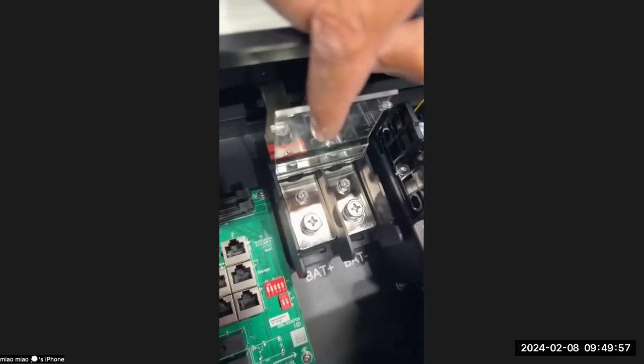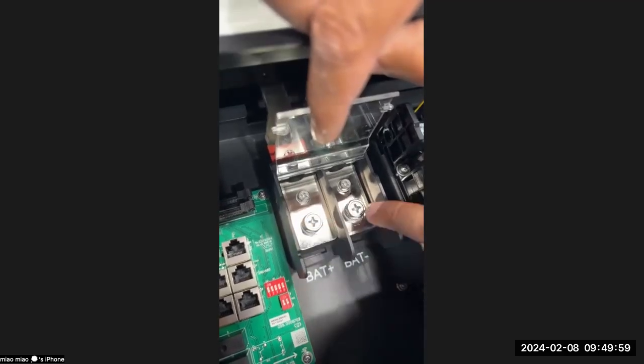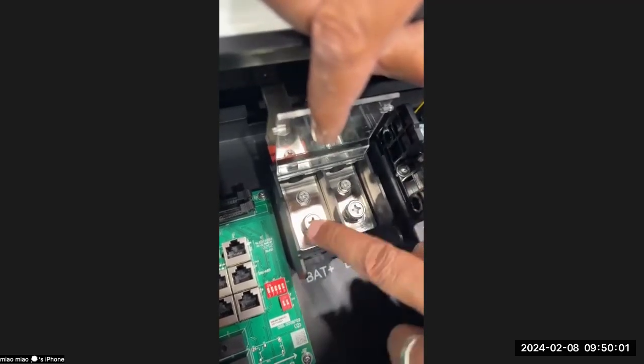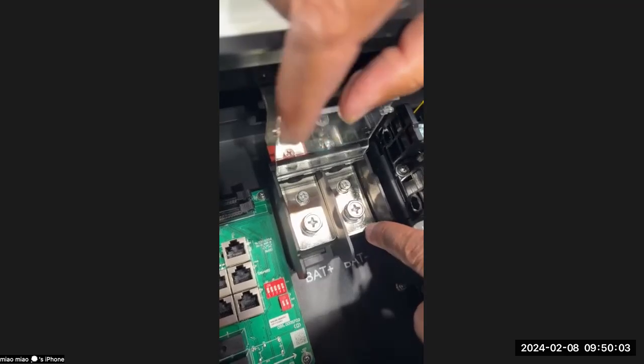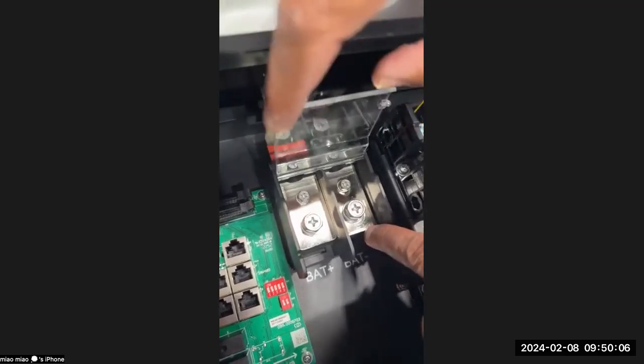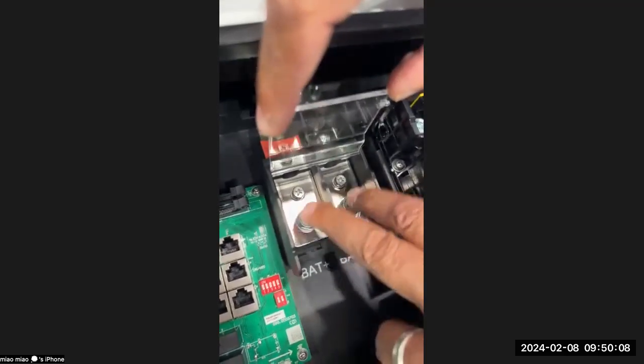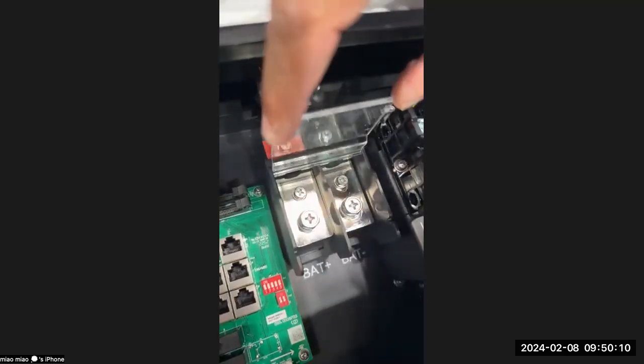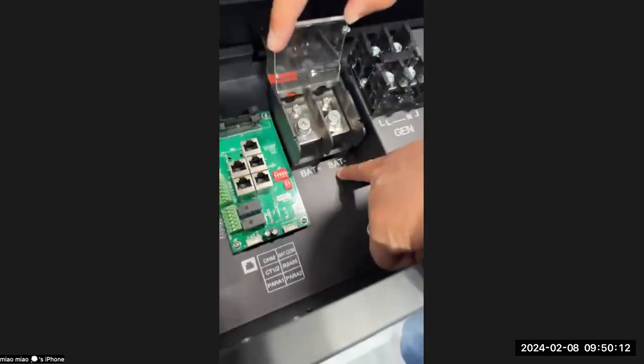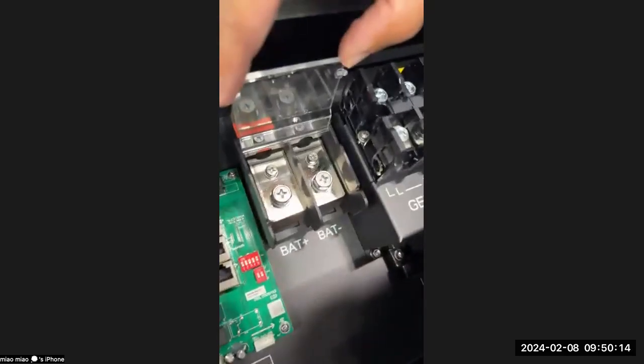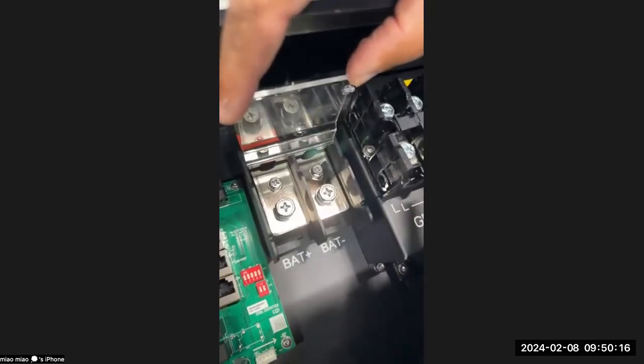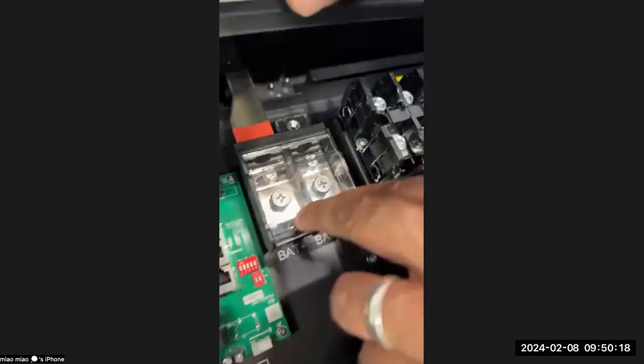I'm not going to go into that now, but the most important thing is that in the manual that we supply with the machines, there's a recommended torque setting for these. Make sure that you torque these down correctly. I know not everybody has a torque wrench or sets torque settings on their drivers, but it is handy to have because a loose connection can run very, very hot. The ports are also adequately marked so that you do not cross or switch your polarity around on the battery.